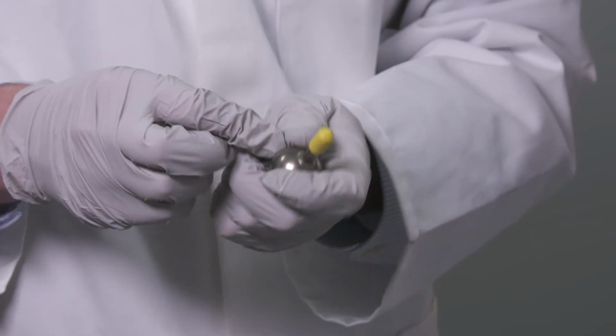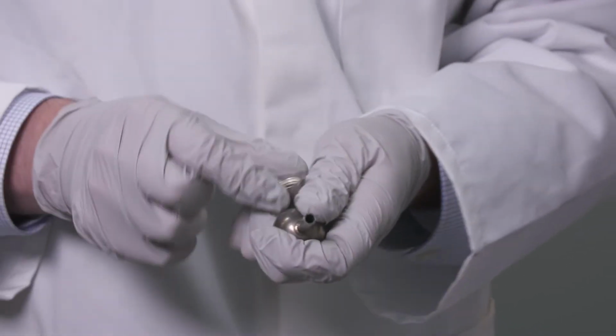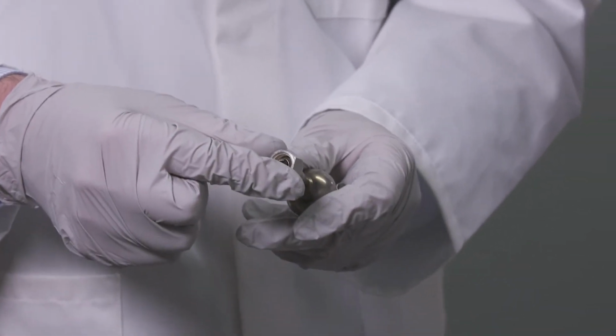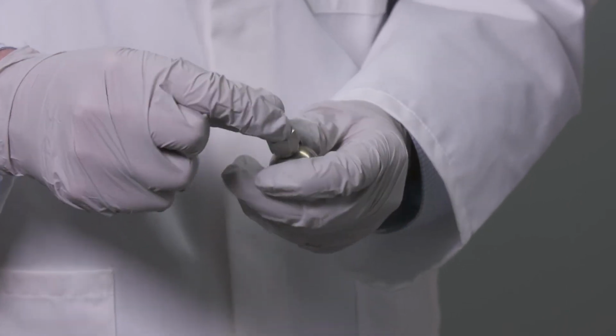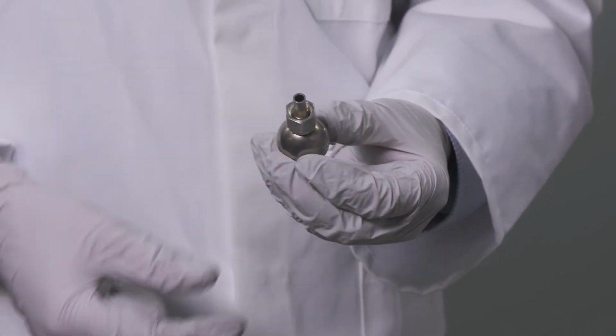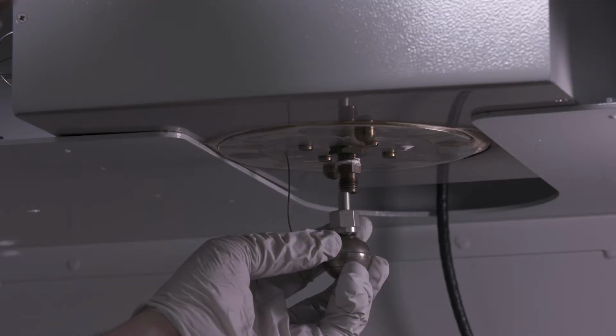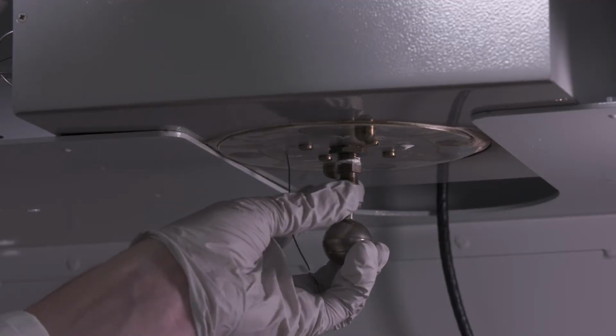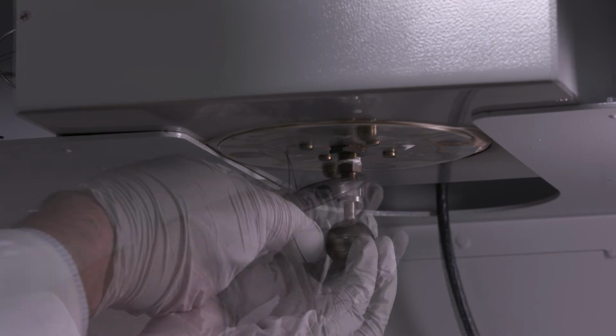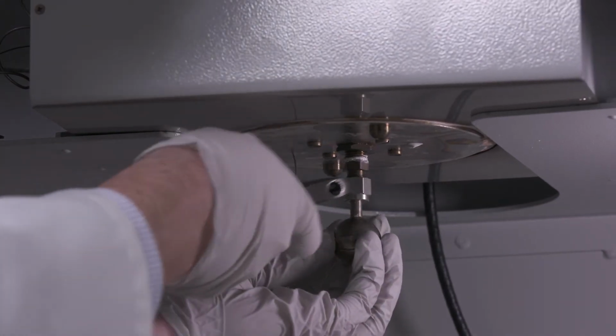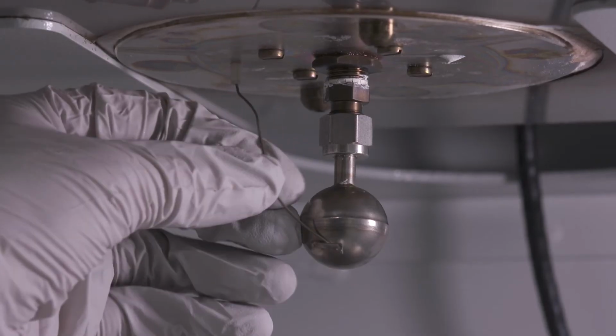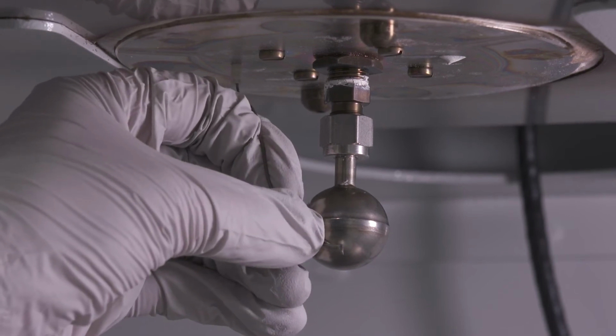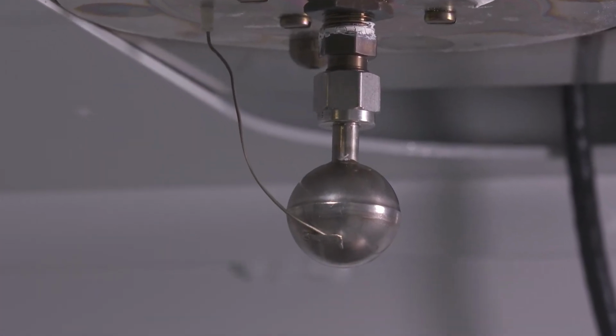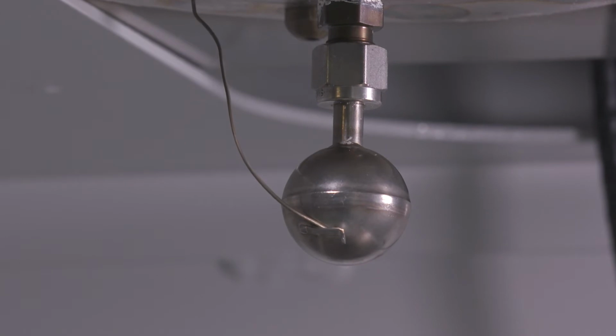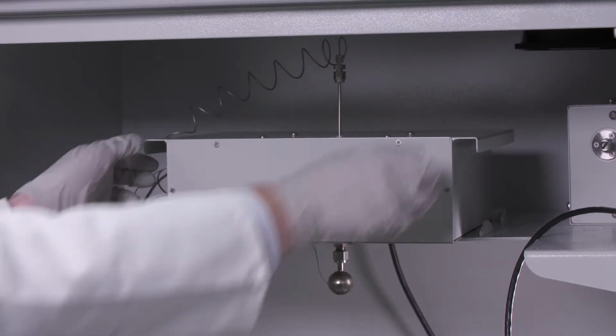Attach a nut and ferrule to the bomb containing the chemical sample. Then attach the bomb to the lid fitting of the calorimeter. Use a wrench to fully tighten the nut to prevent leaks. Attach the bomb thermocouple underneath the clip of the bomb. The tip of the thermocouple must be placed directly under the clip such that the tip does not protrude from the clip. Place the calorimeter lid onto the base.